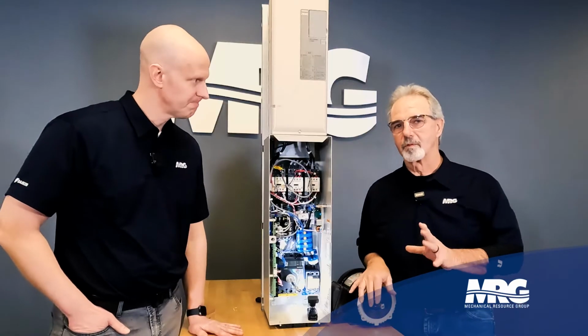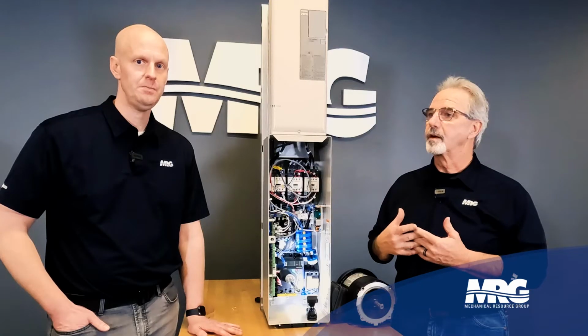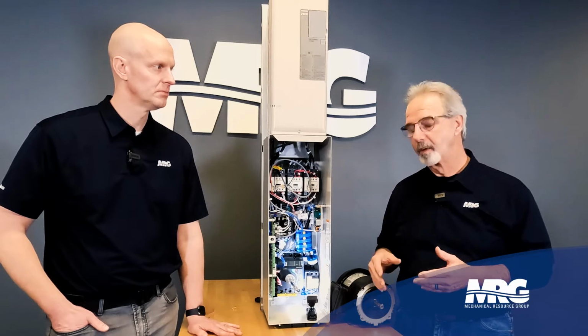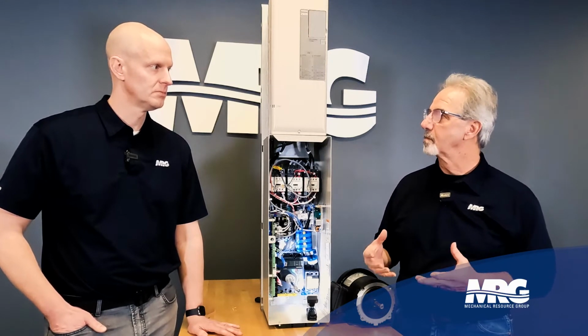Variable frequency drives are a switch device. So what happens is we take an AC, we turn it into DC, and then we switch it at a very high rate of speed. What that does is create a parasitic voltage that travels through the output leads of the drive and enters the magnetic field of the electric motor. It finds a ground path, and the only ground path in electric motors is where the bearings make contact with the motor frame.